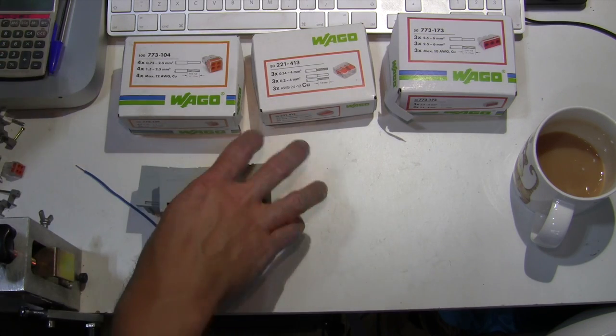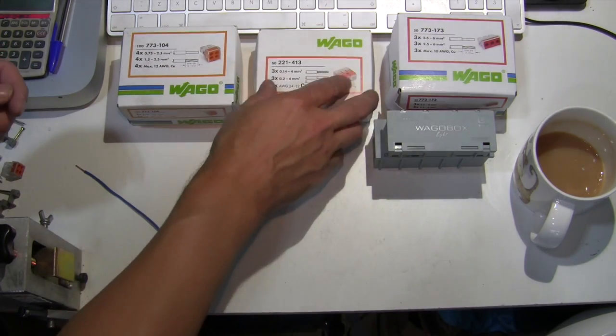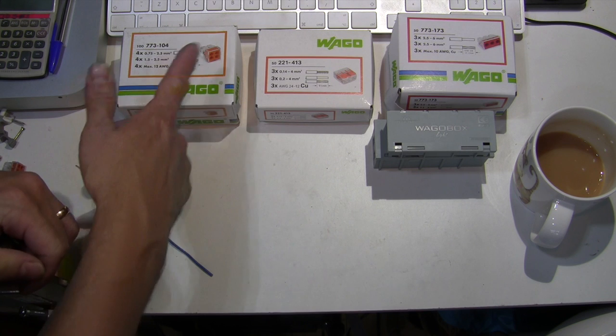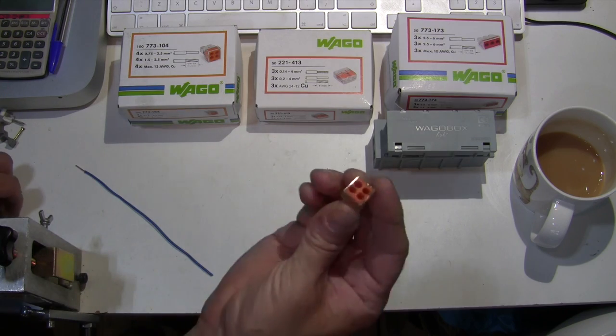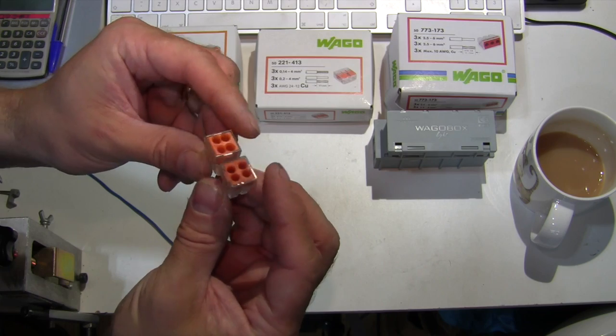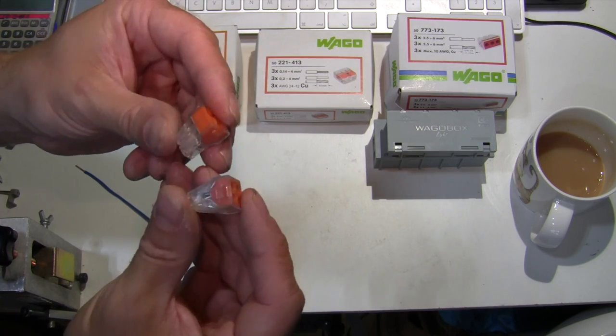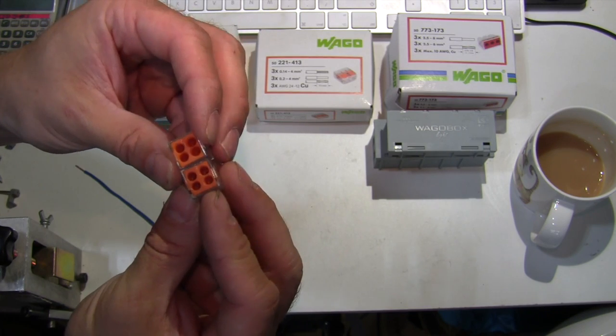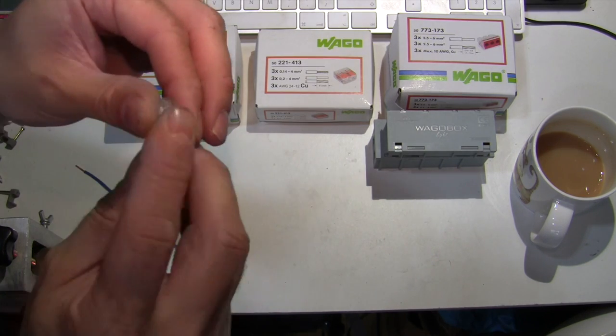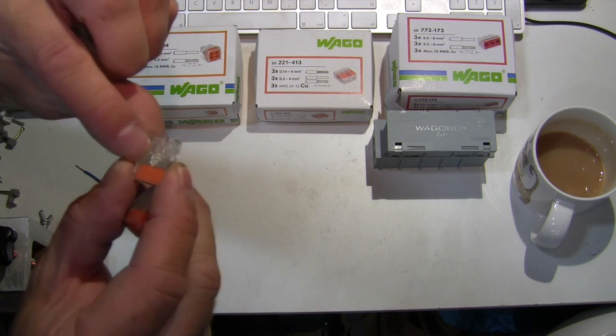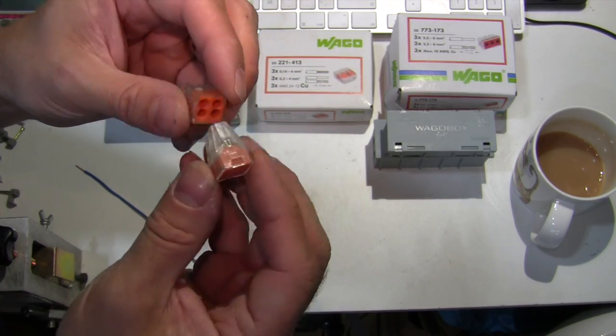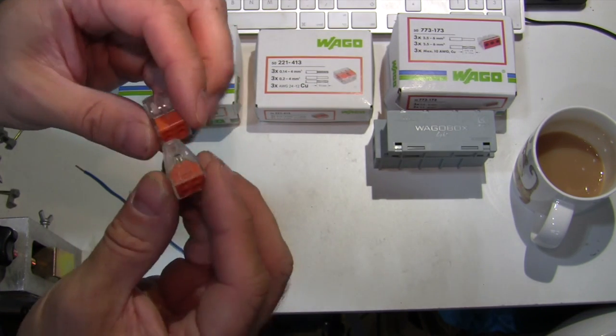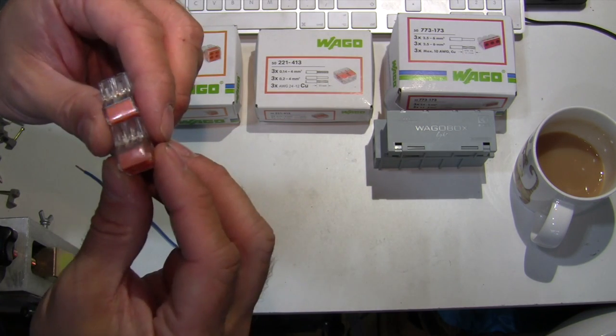The reason I'm talking about these things today is because, like I said, I've just come back from an emergency call out. A few weeks ago, my local branch of CEF tried to get a bit cheap and moved away, started moving away from Wago as a brand, and started putting some other brand on the shelf, which I've got one here. As you can see, we've got one of these is a Wago and one of these is a Fago, a fake Wago. They do look absolutely identical. There is a slightly different coloring to the orange, which the camera's got no hope of picking up, but which you can see to the naked eye. This one is the Wago because it does have the Wago logo etched on there. And this one is the Fago, whatever brand it may be. I'm not going to name names, which looks all intents and purposes like a Wago, is rated exactly the same. Looks like it came off the same production line, but has been made by somebody else.